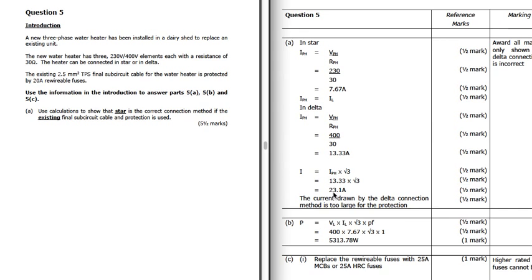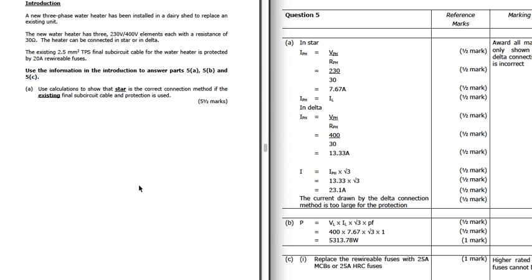And obviously this is much too big for a 20 amp rewirable fuse. So the current drawn by the delta connection method is too large for the protection. So we would use star.